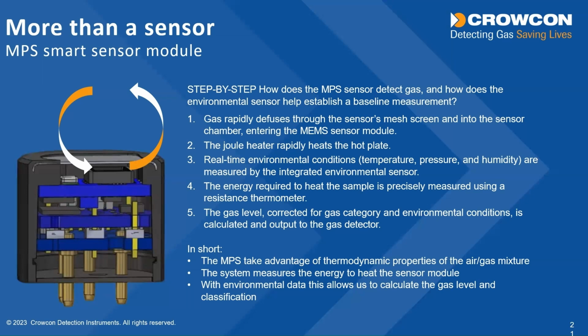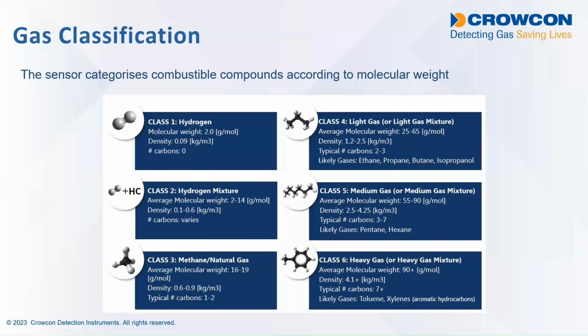And it's just constantly heating up that sensor plate and measuring the amount of energy required to heat it back up to 900 degrees Celsius. And then it compares its results to an algorithm stored within the microprocessor, and from the results it's able to classify the types of gas it's seeing according to molecular weights. So it's able to classify whether there's hydrogen present or slightly heavier or longer chain hydrocarbons in the mix.